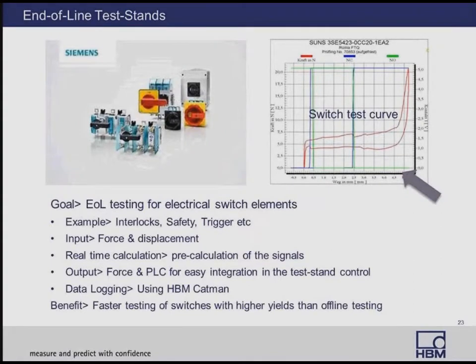End-of-line testing, in this case, is for Siemens electrical switches or switch elements. Examples of such elements are interlocks, safety triggers. Your power companies are a big subscriber of such elements. In this case, the input measurement was force and displacement. So you're plotting force versus displacement, as you can see. The output was force and PLC for easy integration to the test control. So you basically control how much force you need to apply based on how much displacement any of these switch elements are moving, either rotationally or linearly.